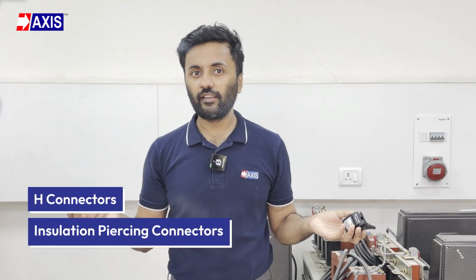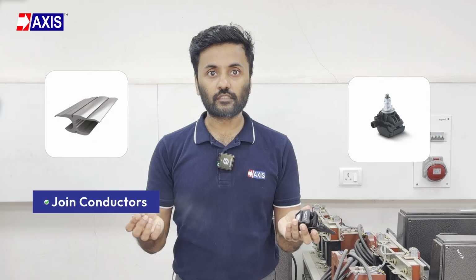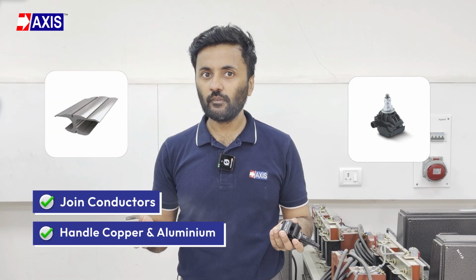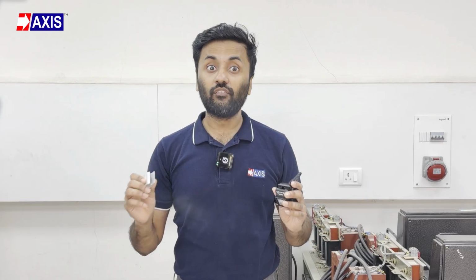You see H connectors and insulation piercing connectors on overhead lines. Both join conductors, both handle copper and aluminium, so you'll assume that they are interchangeable, but they're not. If you pick the wrong one, your connection will fail.